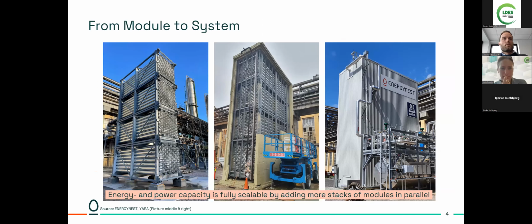And the way we construct a storage is also very simple. We have a concrete foundation with load-bearing elements, as you see on the left side. This picture is taken from our project with Yara in Norway, which is currently in operation. On the left side picture, you see a stack of 4. They are hydraulically connected in the vertical direction. When you charge the battery, we have hot fluid entering at the top, and then cold fluid coming out at the bottom. And then when we discharge, we reverse the flow. And as I said before, we can use water, steam, thermal oils, or also other fluids.